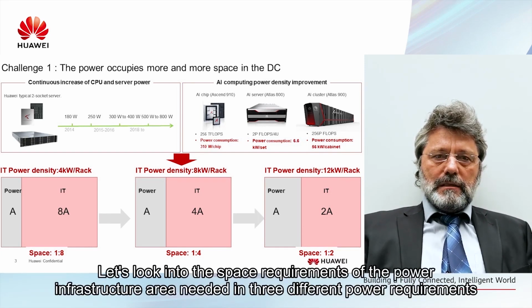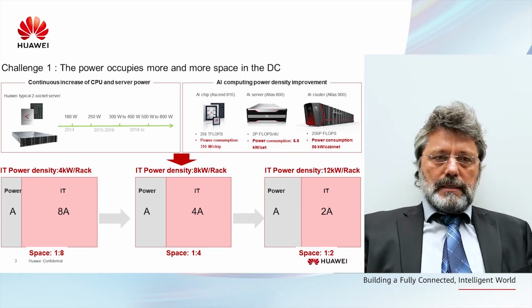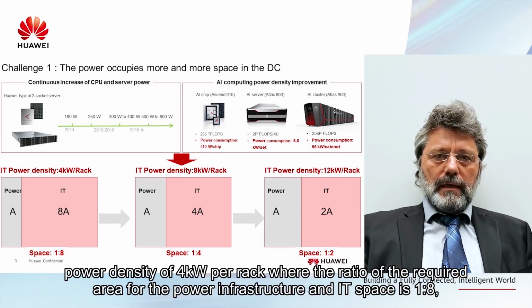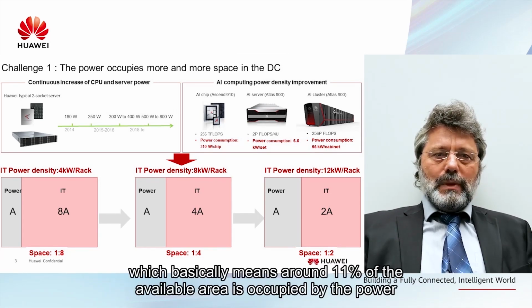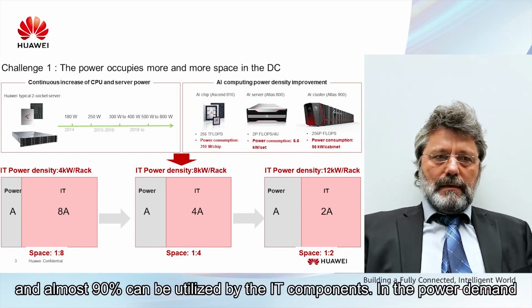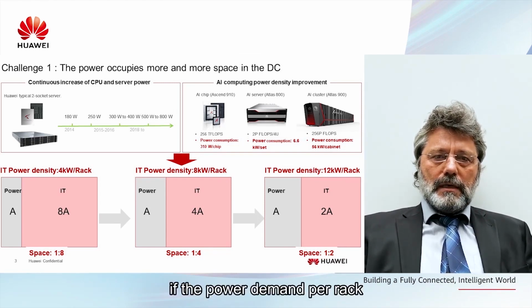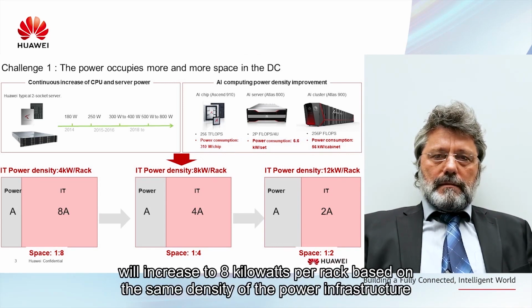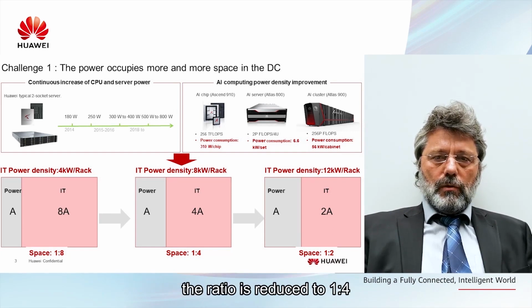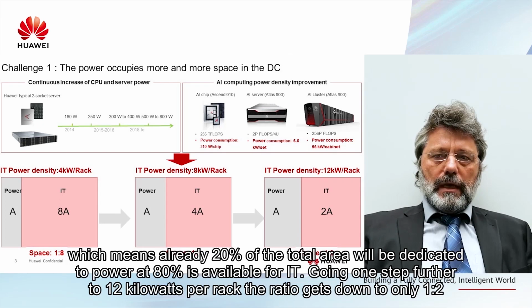Let's look into the space requirements of the power infrastructure area needed for 3 different power requirements per rack. Starting from a power density of 4 kilowatts per rack, where the ratio of the required area for the power infrastructure in the IT space is 1:8, which basically means around 11% of the available area is occupied by the power and almost 90% can be utilized by the IT components. If the power demand per rack increases to 8 kilowatts per rack, based on the same density of the power infrastructure, the ratio is reduced to 1:4, which means already 20% of the total area will be dedicated to power and 80% is available for IT.